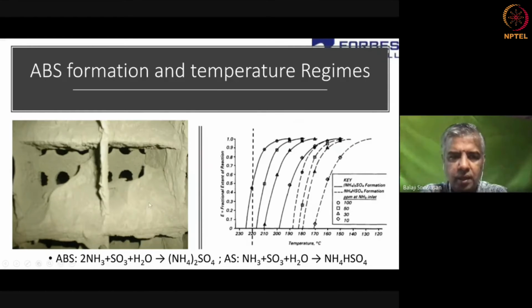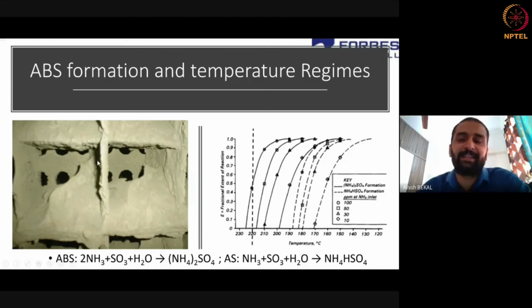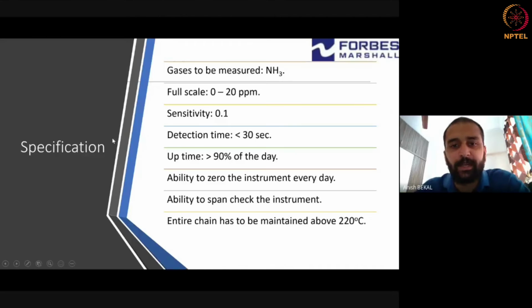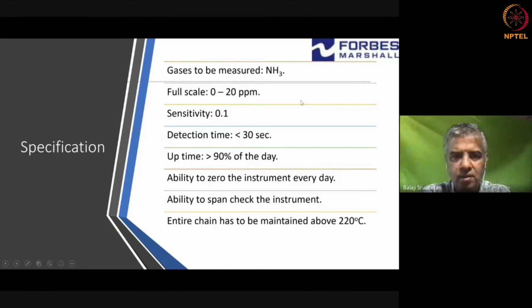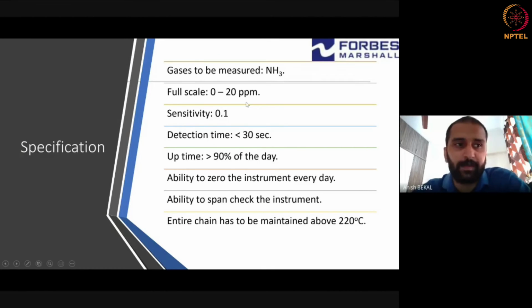Yeah, and there again you need a sensor. You have something called ammonium bisulfate forming because of the sulfur present, and as soon as the temperature goes anything below 220 degrees centigrade, it would just clog your whole power plant. That's where you need an ammonia sensor, which can measure sensitivities of 0.1 ppm.